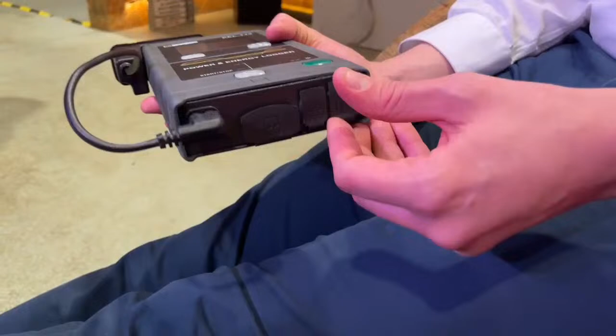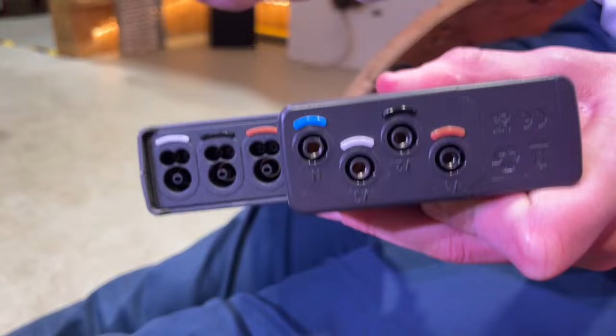Along the top we have a self-powering adapter, so it supplies voltage from V1 and neutral - phase 1 and neutral - into the figure 8 main socket at the bottom. Then we have V2 and V3 for each of the other phases, and also 3 CTs. It works the calculation for the neutral, so it can measure your power and everything.